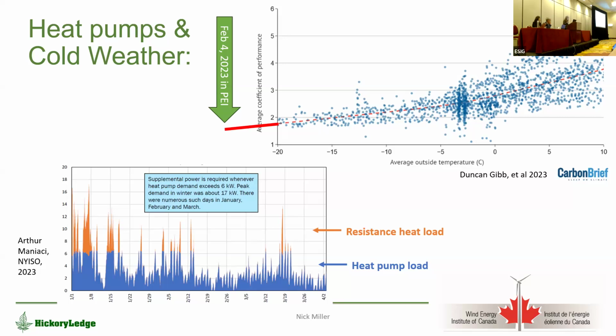This bottom left graphic is from New York ISO, giving you a sense of what the supplemental heat source can look like. For a house in New York, the heat pump load, shown in blue, goes up to about 6 kilowatts. When it gets really cold, especially at the beginning of this period in early January, you can see resistance supplemental heat kicking in, adding about 11 kilowatts extra. So your heat pump load might only be 6 kilowatts, but when it's really cold, that resistance heat kicks in and your load might triple. That's something that can take planners by surprise.